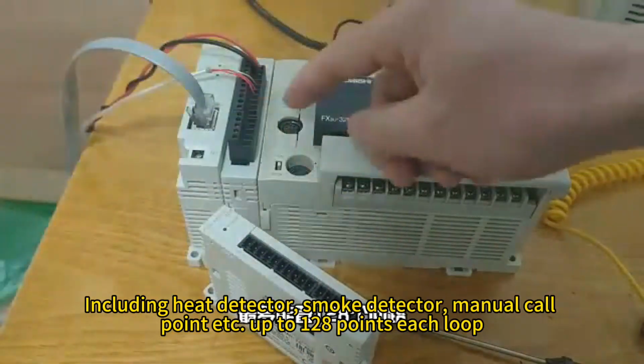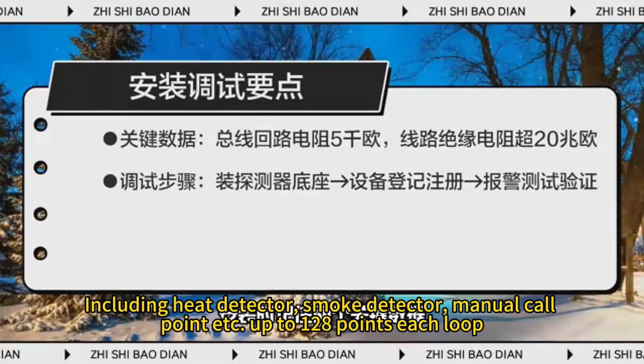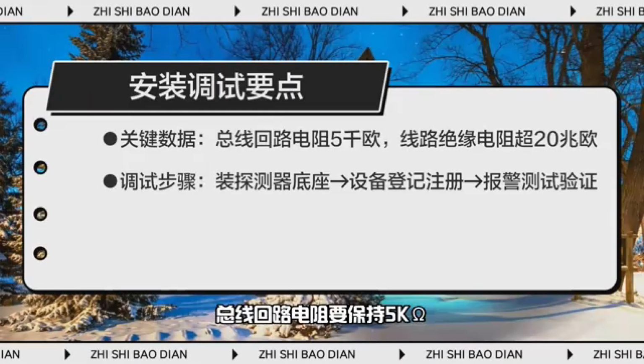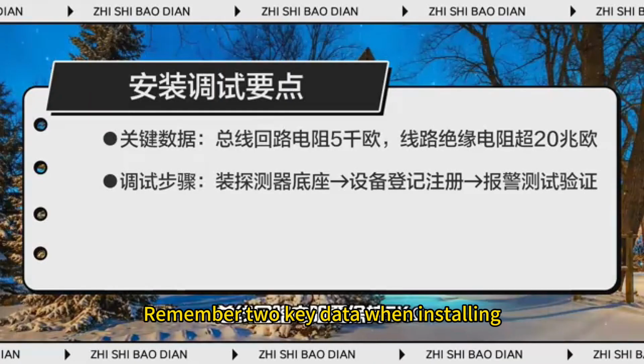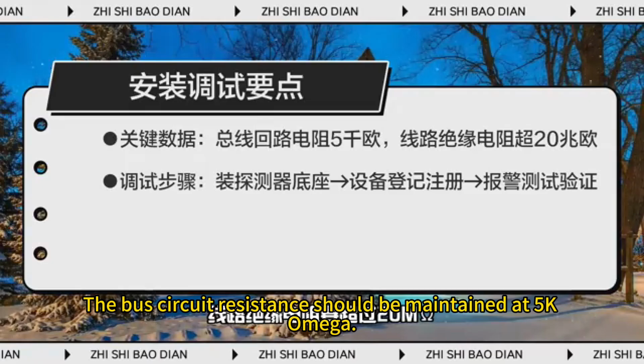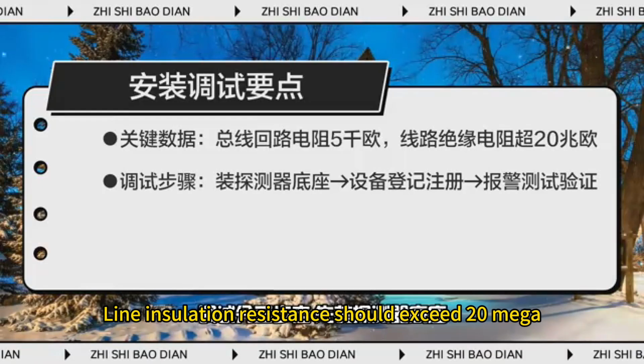It can connect to 15 device types, including heat detector, smoke detector, manual call point, etc., up to 128 points each loop. Remember the key data when installing. The bus circuit resistance should be maintained at 5000 ohms. Line insulation resistance should exceed 20 mega.